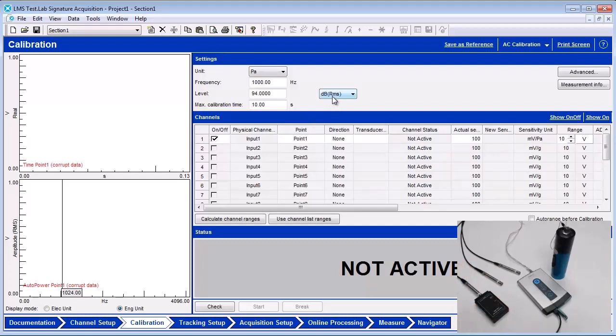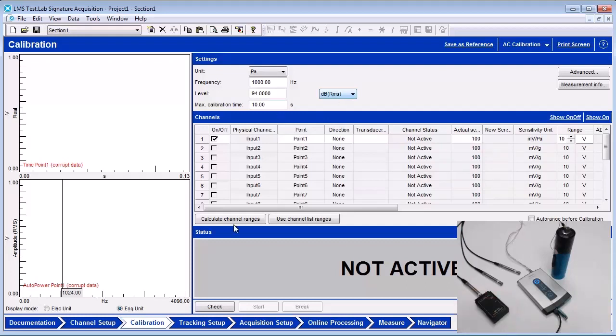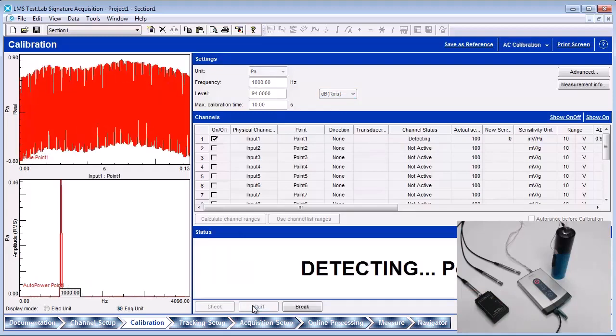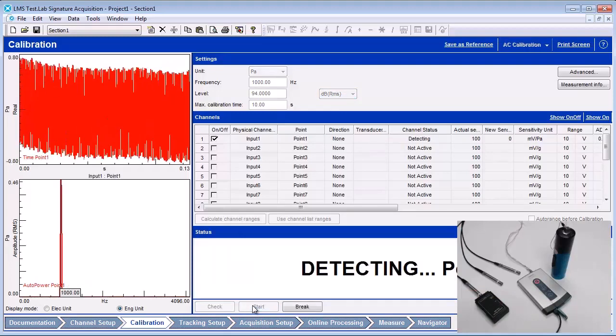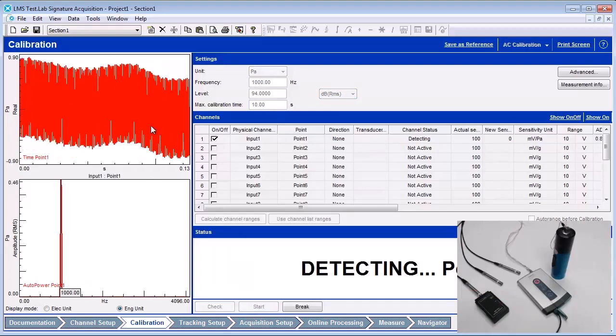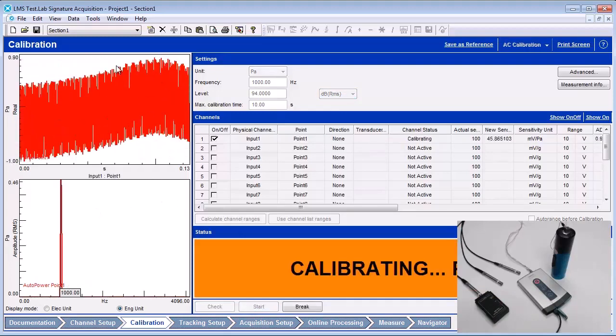Attach the calibrator to the microphone and turn it on. Press the check button and then the start button. The calibration time history and frequency spectrum should show on the left-hand side.